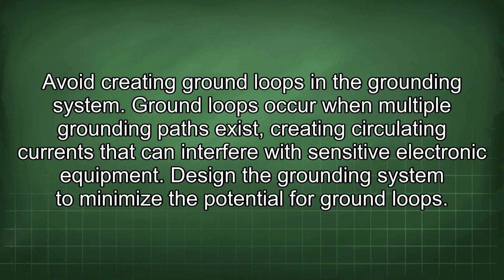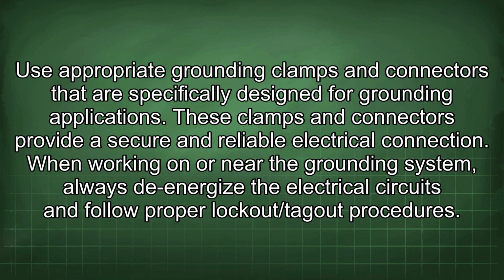Avoid creating ground loops in the grounding system. Ground loops occur when multiple grounding paths exist, creating circulating currents that can interfere with sensitive electronic equipment. Design the grounding system to minimize the potential for ground loops. Use appropriate grounding clamps and connectors that are specifically designed for grounding applications. These clamps and connectors provide a secure and reliable electrical connection.